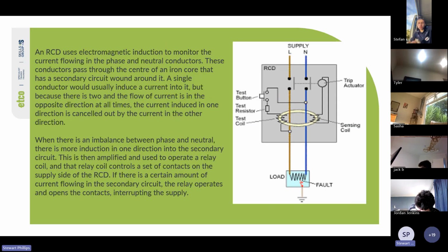Cool. So this is an example drawing of the inside of an RCD. You've got the sensing coil, which is also known as a toroidal coil, and it's got the phase and neutral flowing through it. Because the phase and neutral flow through it, the induction caused by the current flowing through the cables is negated by each other because they're in opposite directions, meaning there's no current flow in the coil. But as soon as there's current flowing in the coil, it will generate enough current to activate the trip actuator, which will disconnect both sides of the line and neutral from the circuit.